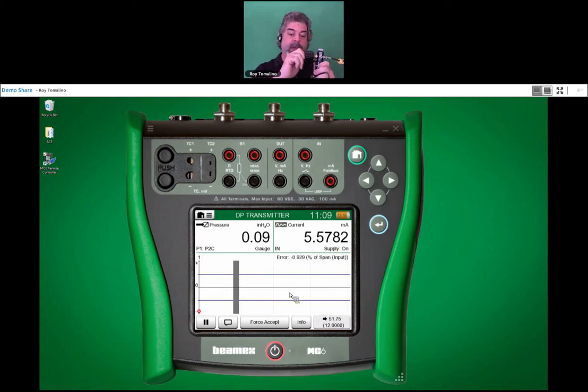So let me close my vent. And what I'm going to do is I'm just trying to get it into the gray bar. This is a predefined area that I've already set up, which is 4% of my target. This is not the tolerance. This is how big of a target. How close do you want to get to my test point? My test point on the bottom right?